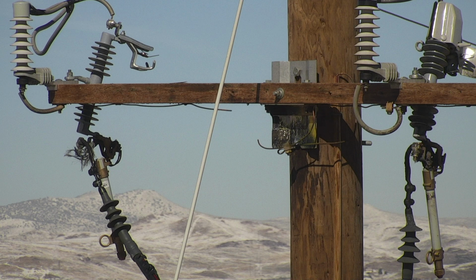This is C phase, that's B phase. So it started here at C phase, and it blew this away, and you'll see that in another image. But you can see that this ground wire for the surge trap is bare copper. It's insulated here, but turns to bare copper where this fuse holder is. If you got 25 kV within probably 2 or 3 inches of that copper wire.